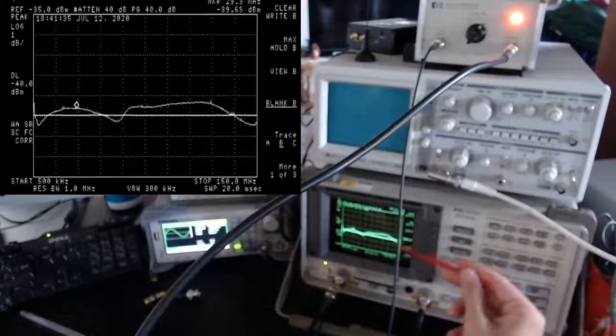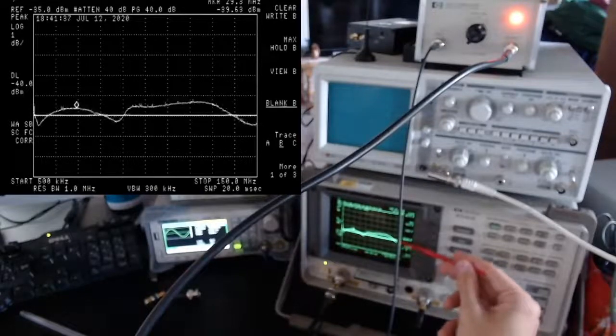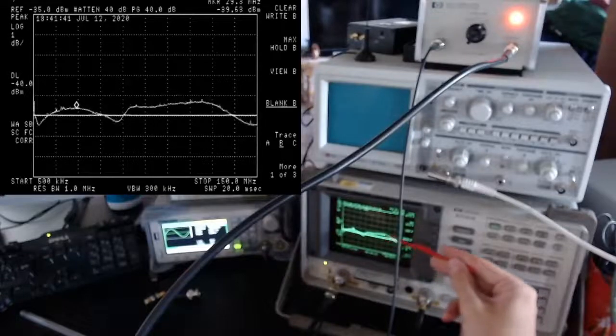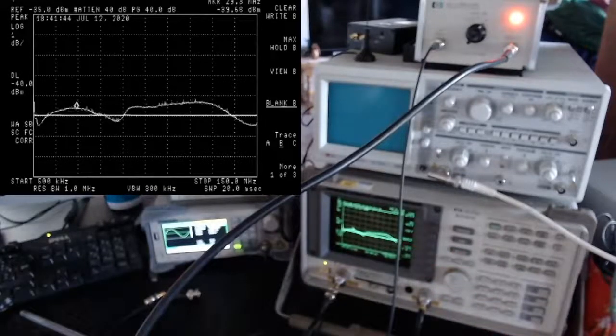At the moment we have only one dB for each division. So this means that amplification is 40 plus or minus one. It's within specification.